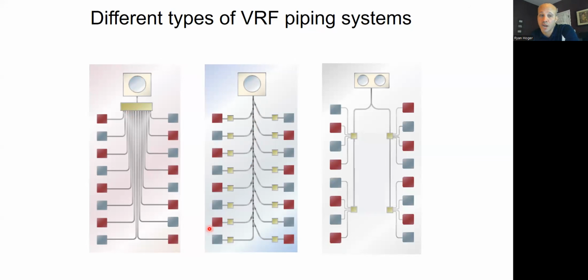I don't want to run piping from every classroom back to that box. It's a lot of extra piping. I've got to fit all that in and buy all that copper. However, if my unit is going into a square building and it's going to go right in the middle, and I can branch off into different directions, kind of like in a star, maybe this one on the left is a better choice for me, depending on how my building is laid out.